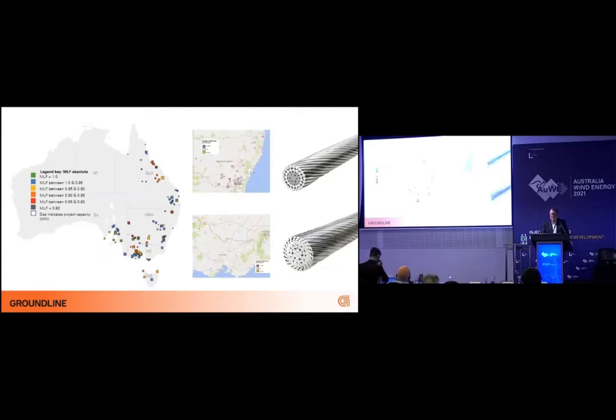The line losses are quite significantly different, and it's interesting to see which new long transmission lines, or old ones reconducted, are going to install AAAC 1120. Comparing the two over a 300 kilometre long line, a typical line, the difference in line losses using the World Bank model is approximately $1 million a year. If you take a less conservative one, 3 or 4 times that.